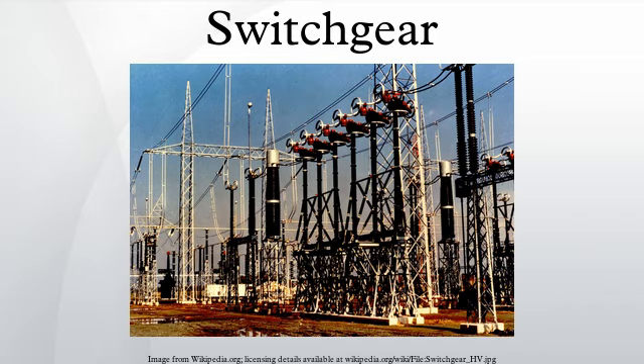Circuit breakers fall into these 5 types. Oil circuit breakers rely upon vaporization of some of the oil to blast a jet of oil along the path of the arc. The vapor released by the arcing consists of hydrogen gas. Air circuit breakers may use compressed air or the magnetic force of the arc itself to elongate the arc. As the length of the sustainable arc is dependent on the available voltage, the elongated arc will eventually exhaust itself. Alternatively, the contacts are rapidly swung into a small sealed chamber, the escaping of the displaced air thus blowing out the arc. Circuit breakers are usually able to terminate all current flow very quickly, typically between 30 ms and 150 ms depending upon the age and construction of the device.